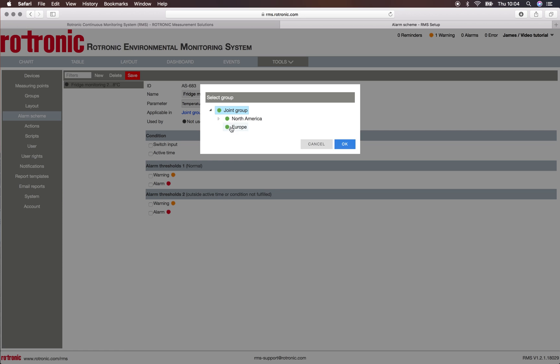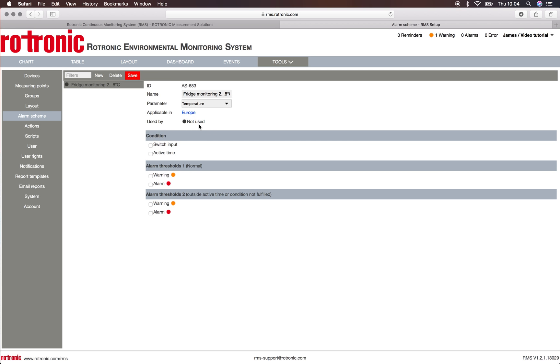Here we're talking about temperature. It is applicable — I go to the group and I say 'Europe', as in Europe and America they can have different standards. At the moment it's not used. Then we can set various conditions: does a switch input have to be activated, is there an active time? And then we can put down the thresholds. Threshold one is for the normal working period, and threshold two is outside of the active time condition.